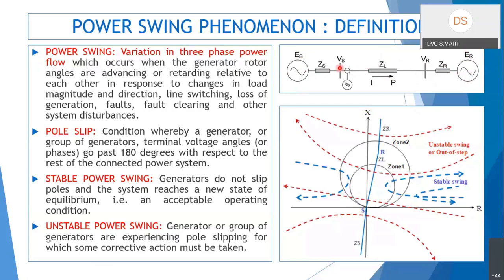When discussing power swing, think of the network in terms of equivalent generators. A stable power swing is one where the generators do not slip poles and the system reaches a new state of equilibrium — an acceptable operating condition different from the previous one.